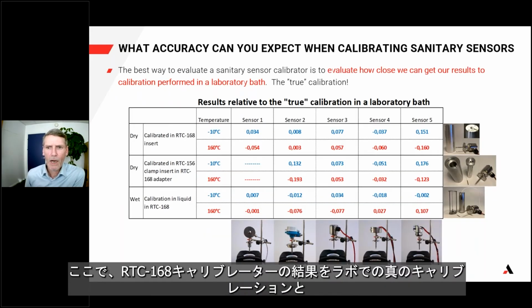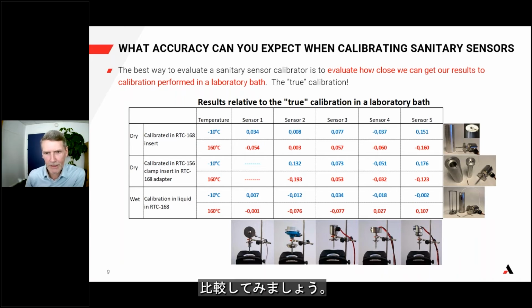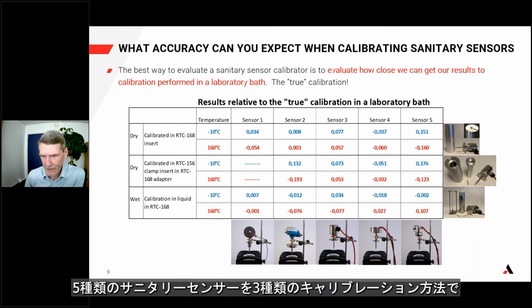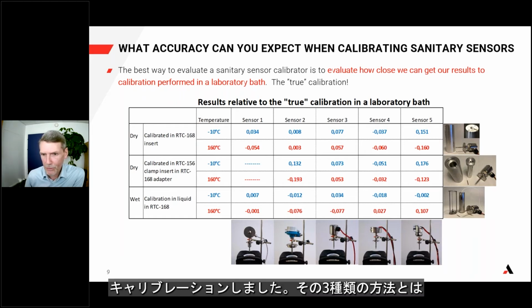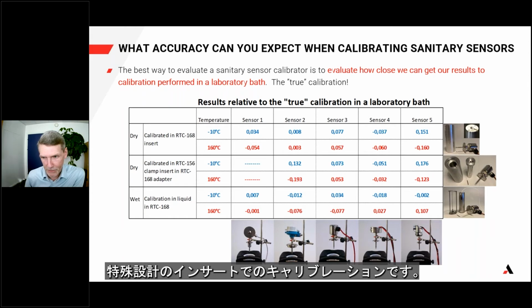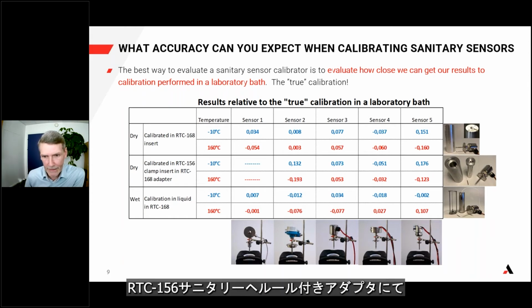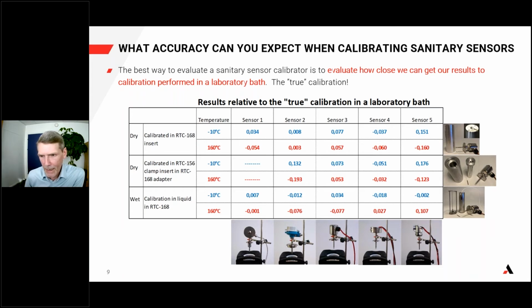Now we compare our RTC 168 calibrator result with that of a true calibration in a laboratory bath. We have made a very thorough test. We have performed a whole matrix of tests. 5 different sanitary sensors have been calibrated with 3 different calibration methods. The 3 methods are: calibrated in a special design insert, in an adapter with RTC 156 sanitary clamp, and finally in a bath.